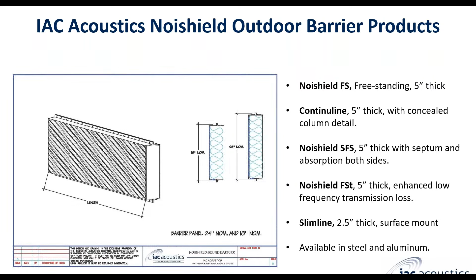This is a cross-sectional view of our panels, typically 18 or 24 inches tall, horizontally laid down and vertically stacked. One important design point: on the perforated side, or left side of the cross-section, the perforation goes halfway through the bottom of the panel. This allows you to wick away moisture and let water from outdoor weather drip away more easily and cleanly, so you don't have pooling inside the panels.